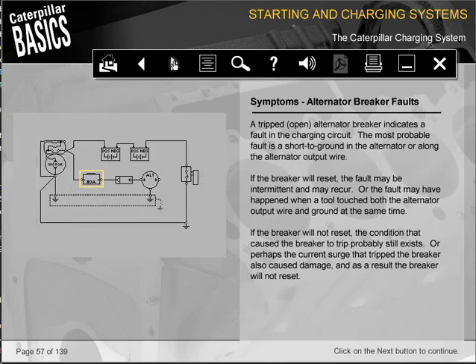A tripped, open alternator breaker indicates a fault in the charging circuit. The most probable fault is a short to ground in the alternator or along the alternator output wire. If the breaker will reset, the fault may be intermittent and may recur. Or the fault may have happened when a tool touched both the alternator output wire and ground at the same time. If the breaker will not reset, the condition that caused the breaker to trip probably still exists. Or perhaps the current surge that tripped the breaker also caused damage, and as a result the breaker will not reset.